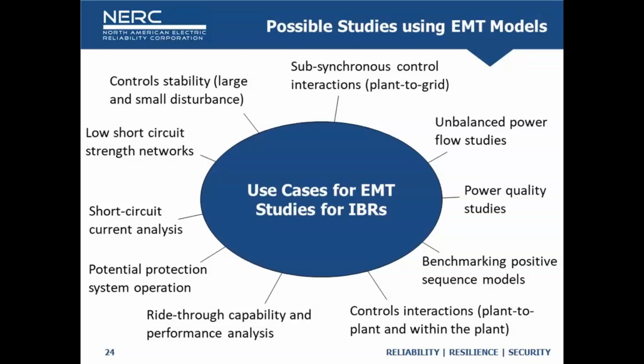But get that early, even if you aren't planning to run an EMT study, get the model. Because 10, 15 years from now, when your super strong grid becomes a weak grid because a bunch of synchronous machines retired for various reasons, you may have a large pocket that went from a strong grid to a low short circuit grid, and you've got to run low short circuit type studies unexpectedly.